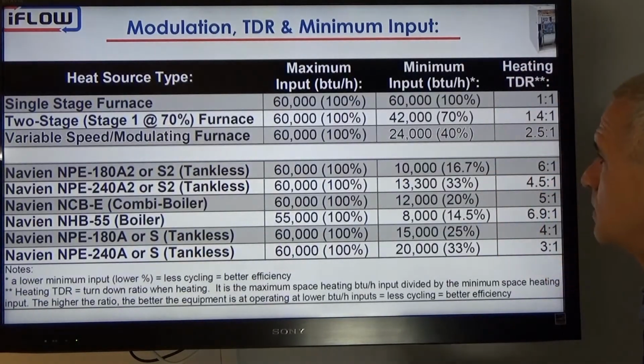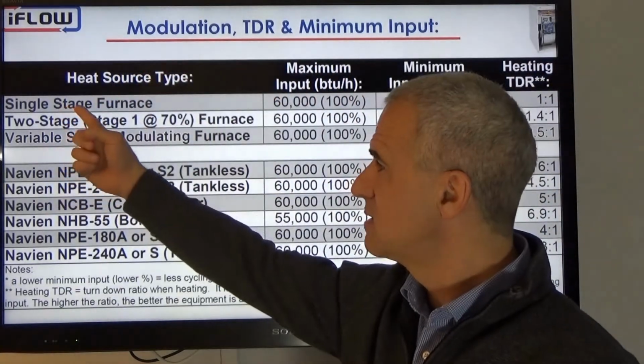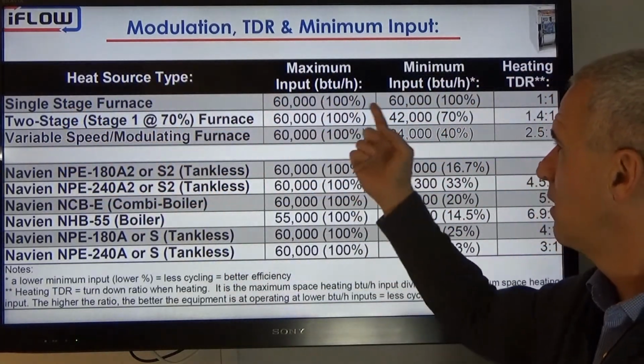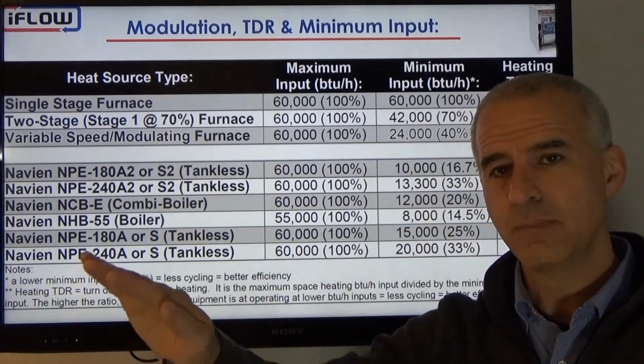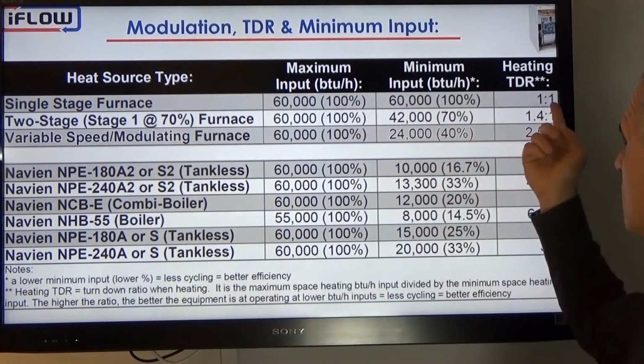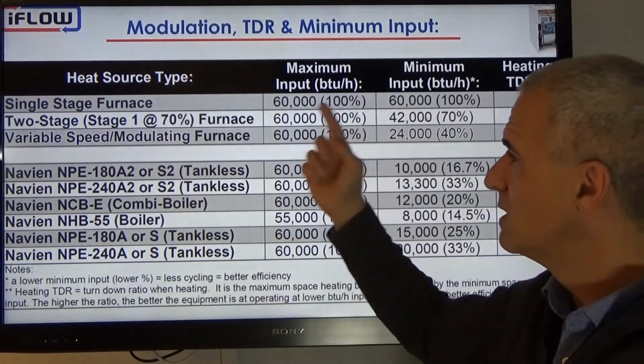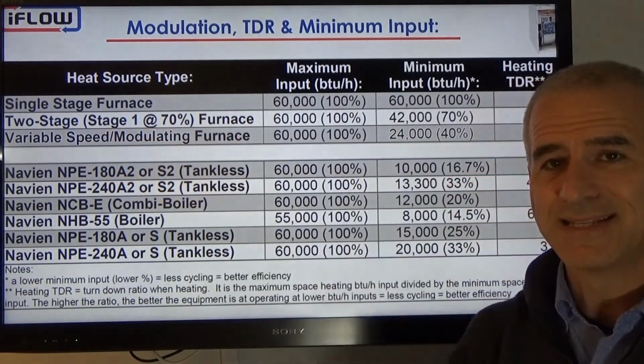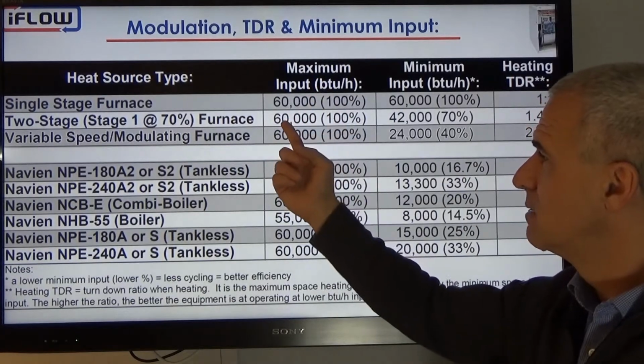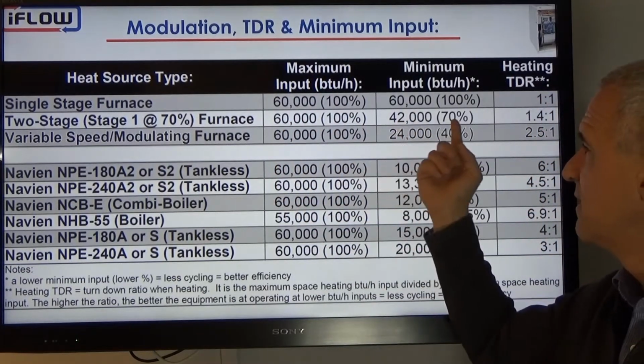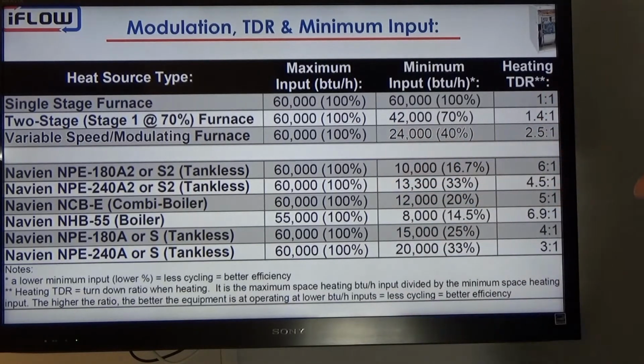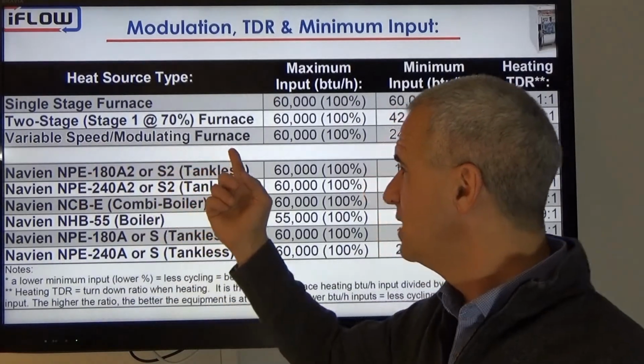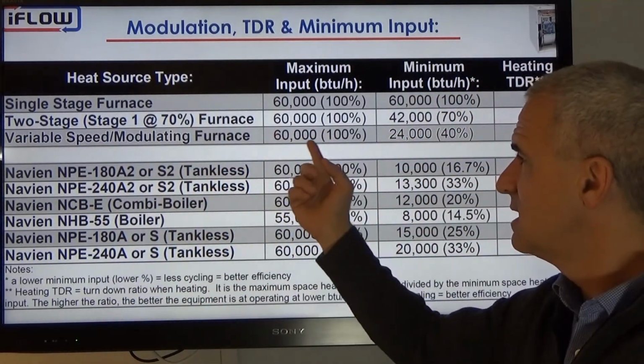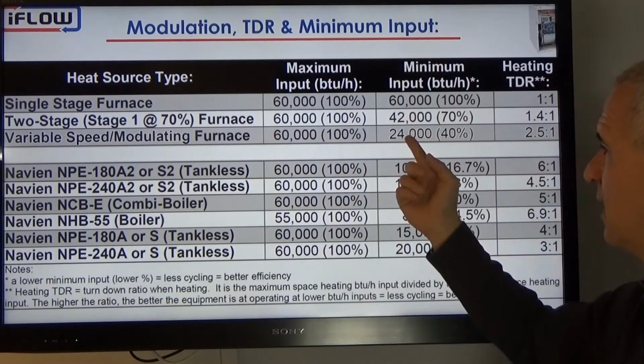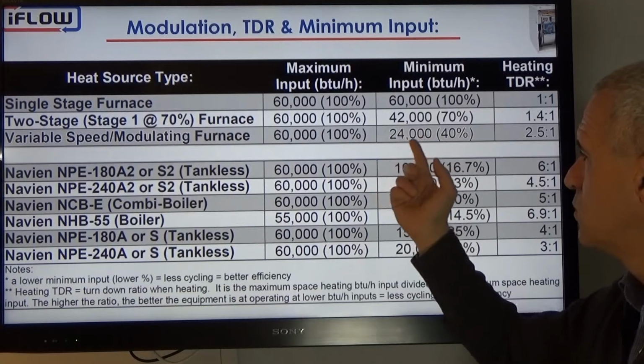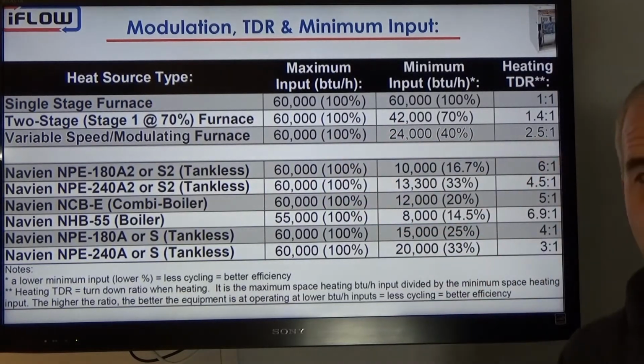So let's compare those. A furnace, let's talk about a single stage furnace, 60,000 BTUs. You know it's single stage, it comes on at 1. It fires at maximum and then cycles on and off. So it has a turn down ratio of 1. Only 1 speed. Let's take a 2-stage furnace where stage 1 is at 70%. So maximum would be 60,000. Minimum would be 70% of that, or 42,000, which gives us a turn down ratio of 1.4 to 1. The variable speed modulating furnaces that we just looked at, again, 60,000 BTU, we know that they could modulate, the Carrier one modulated down to 40%, which was 24,000 BTUs, giving us a turn down ratio of 2.5 to 1.